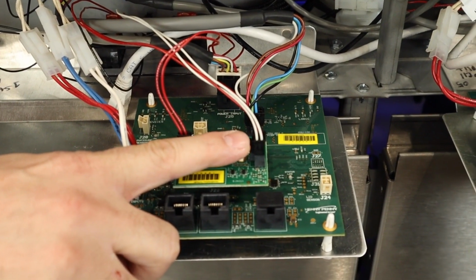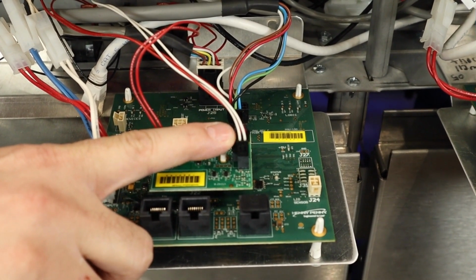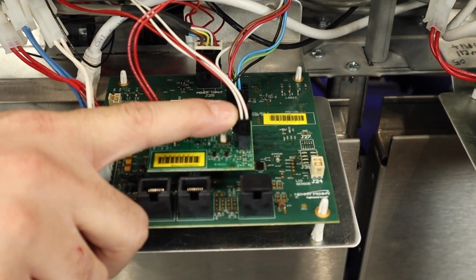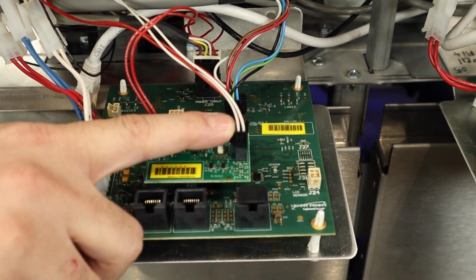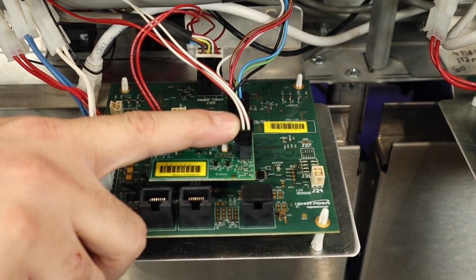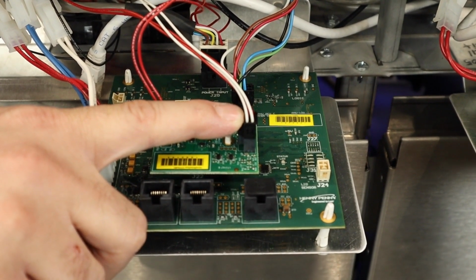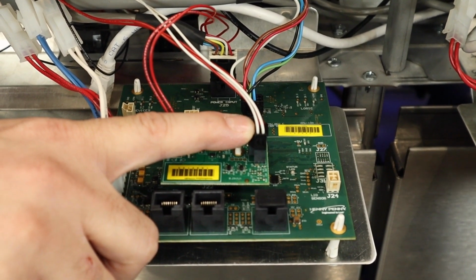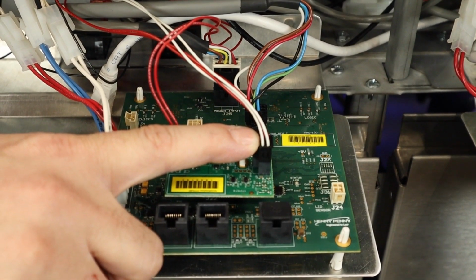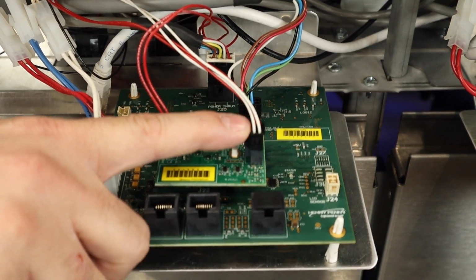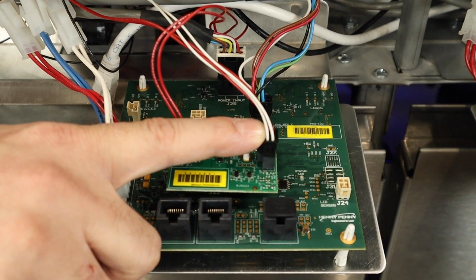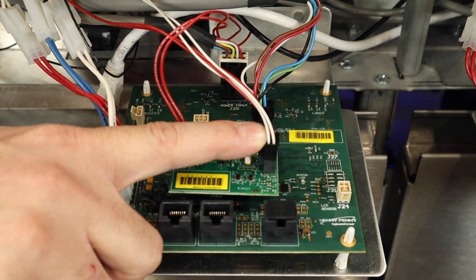For full VATs, there will be 2 wires per probe and 2 probes per VAT for a total of 4 wires. For full VATs, we will need to check both probes as either probe can cause the error. For split VATs, you will only have to check 1 probe. To check that probe, we can unplug it from our PMU board here and then use our meter leads to insert into the connector and check the resistance reading to compare to the chart and see if it matches the temperature of our oil. Remember that we are using the 100 ohm scale at 32 degrees for the high limit.